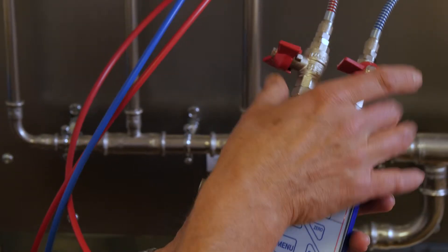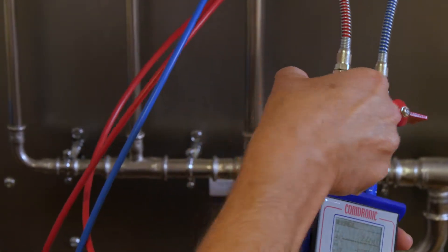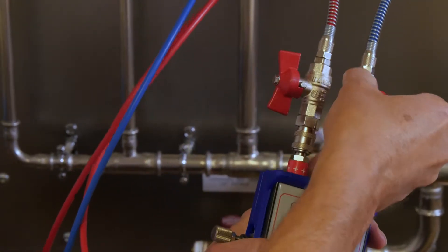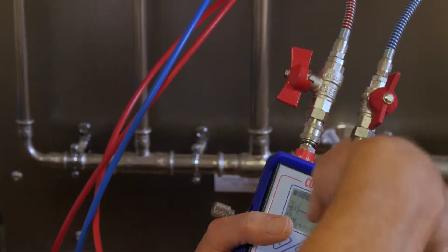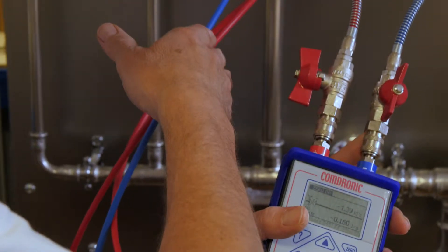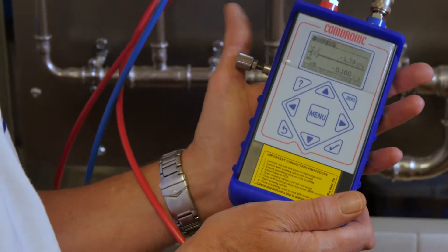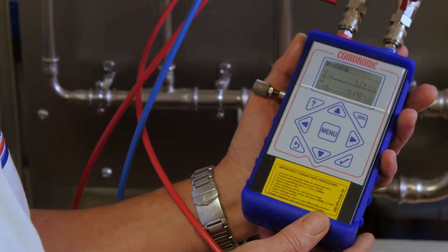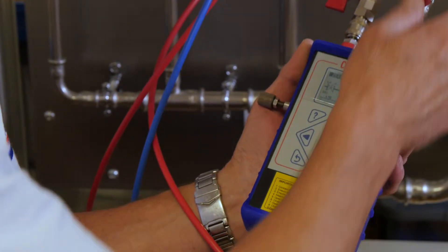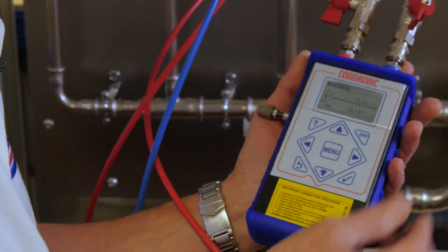So we've connected the tubes with the valves closed. We're now going to open the valves on the unit to allow any air to purge through the system from the high pressure side to the low pressure side. Once that's completed it might take a couple of minutes. But once that's completed and you can't hear any air moving that's fine.